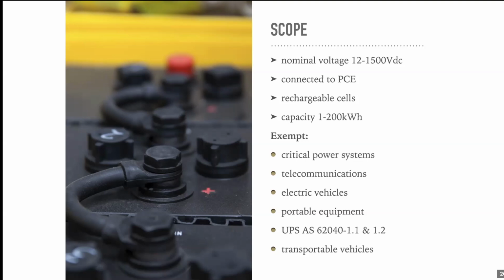Now, don't take that as a given. We'll look at some of those location requirements. It doesn't cover portable equipment, so if it's not a part of a fixed installation, it's exempt. And if it's a UPS system for critical power supplies or essential power covered by an existing standard, AS 62040, so it's not a grid paralleling system, it's just a backup system, independent, then it's exempt. And of course, transportable vehicles.